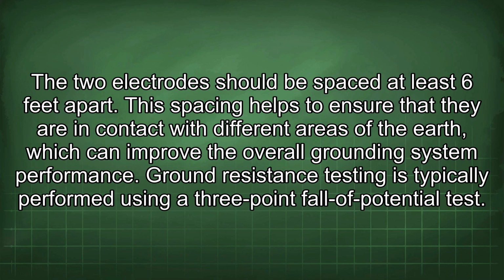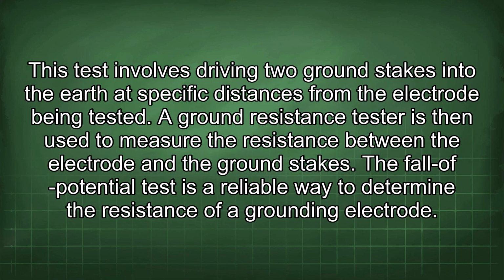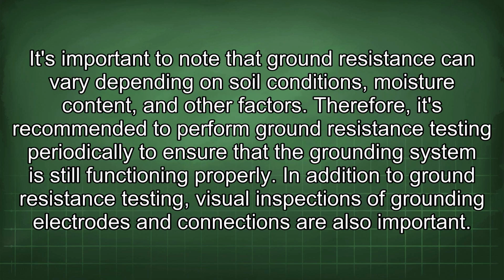Ground resistance testing is typically performed using a 3-point fall of potential test. This test involves driving 2 ground stakes into the earth at specific distances from the electrode being tested. A ground resistance tester is then used to measure the resistance between the electrode and the ground stakes. The fall of potential test is a reliable way to determine the resistance of a grounding electrode. It's important to note that ground resistance can vary depending on soil conditions, moisture content, and other factors. Therefore, it's recommended to perform ground resistance testing periodically to ensure that the grounding system is still functioning properly.